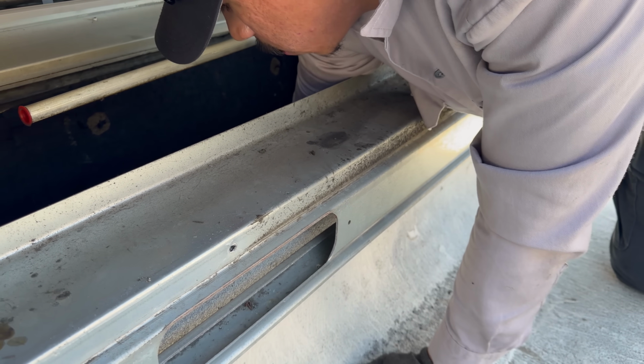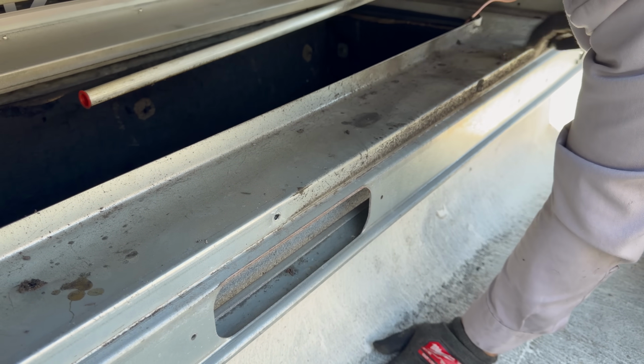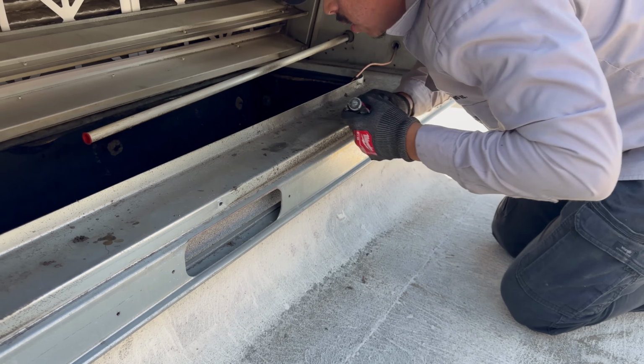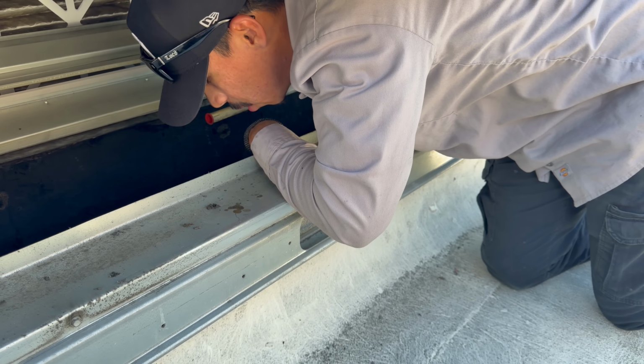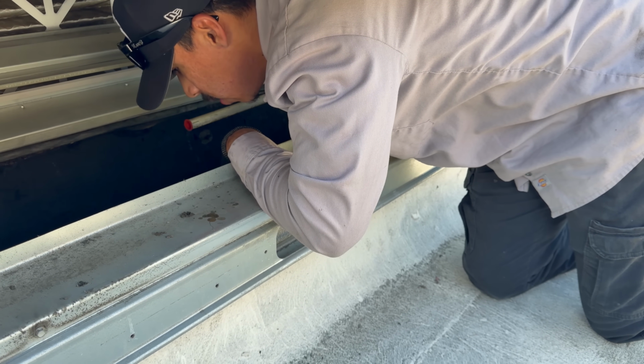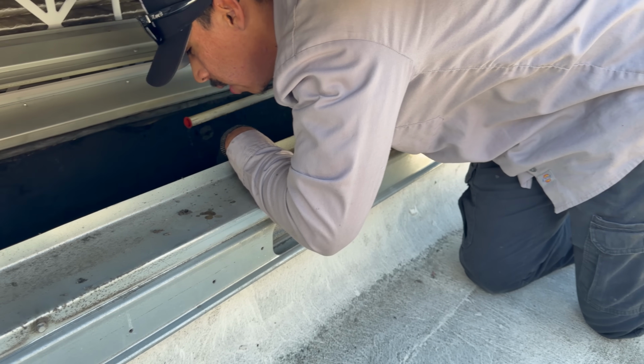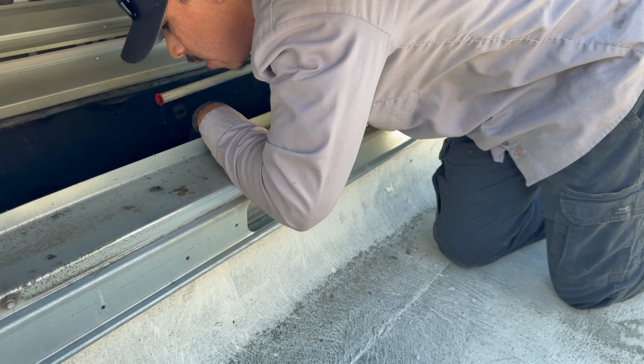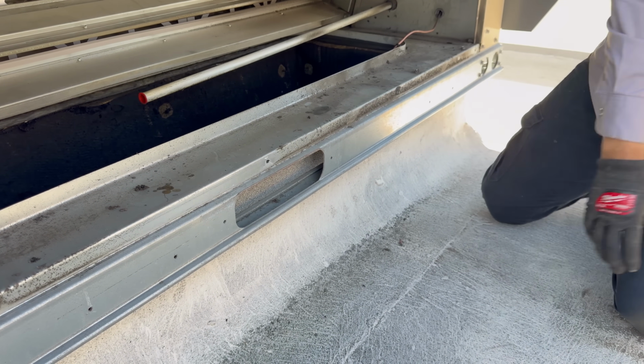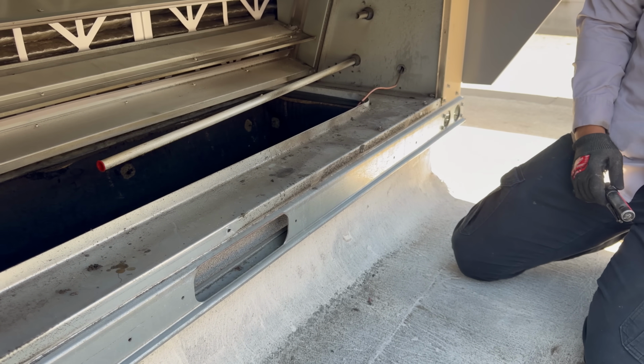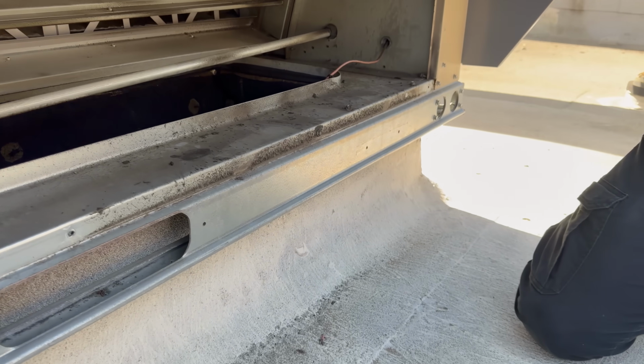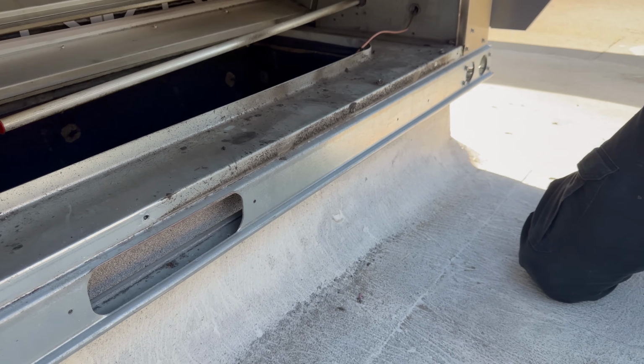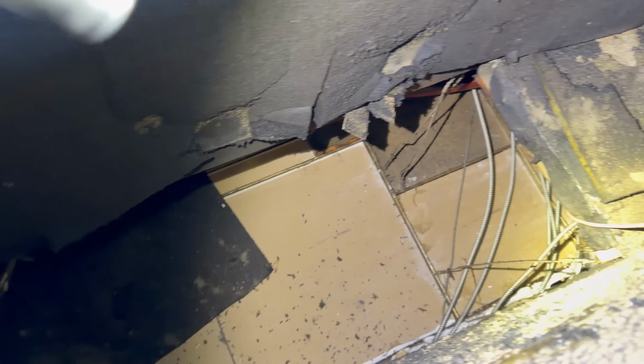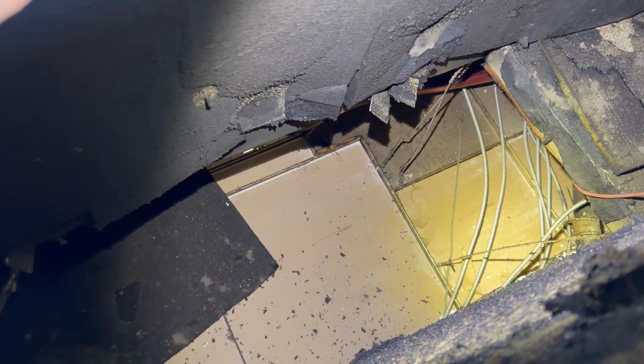Or is that a thermostat wire? Is it just dropped down in the duct, or is that, that might be the actual thermostat wire? I think it's a thermostat wire. Oh, so the zone sensor, this guy, I wonder where the zone sensor is. I don't know where it is. It's interesting. I thought it was dropped down here. We're gonna have to go check. But it could be, let's see, let me see your flashlight. Oh geez, they have an attic return. I remember this now. Yeah, that's not right.